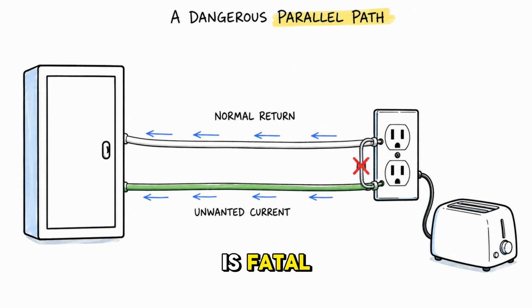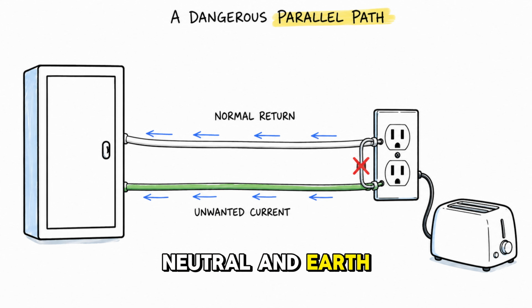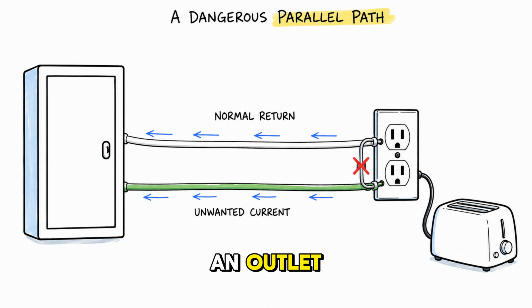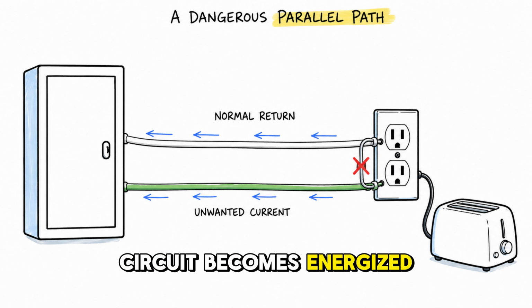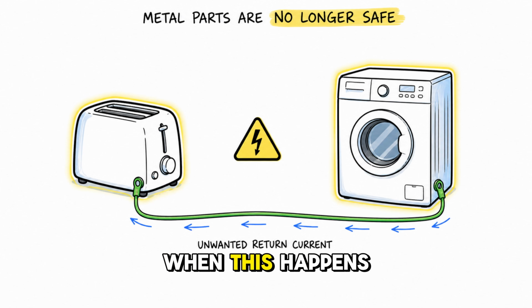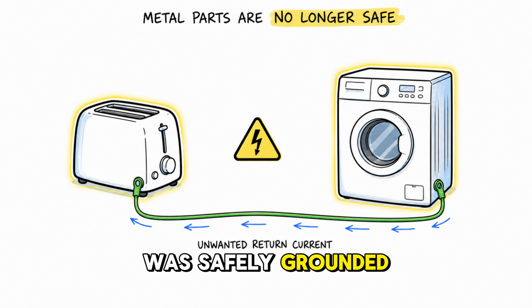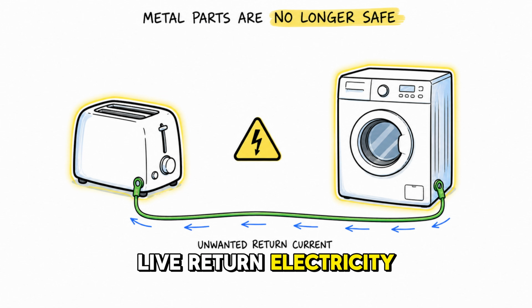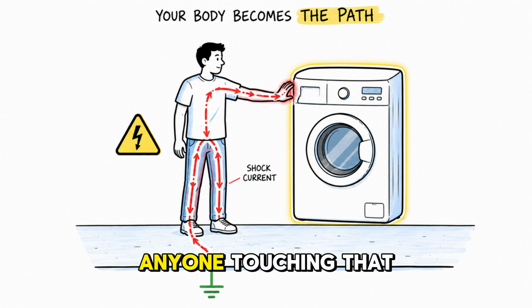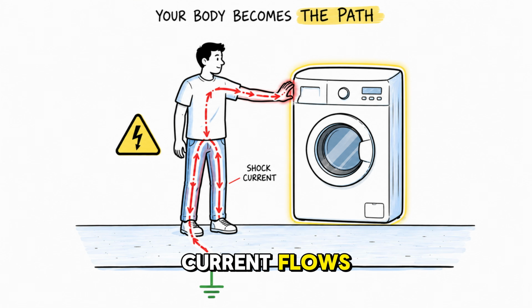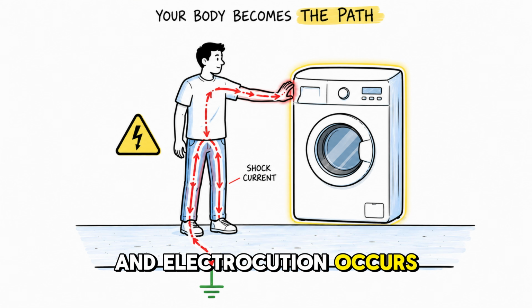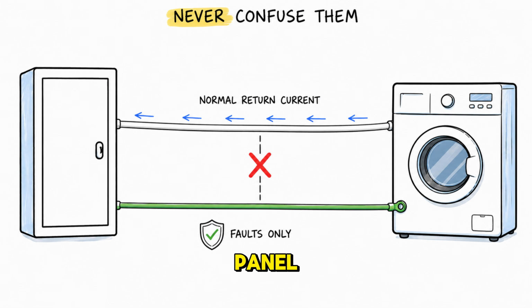Now here is why confusing them is fatal. If you connect the neutral and earth wires together at a subpanel or at an outlet, you create a parallel path. The earth wire in that circuit becomes energized with return neutral current. When this happens, the metal chassis of every appliance on that circuit, which you assumed was safely grounded, is now carrying live return electricity. Anyone touching that metal casing provides a path to the floor. Current flows directly through their body and electrocution occurs. Both wires connect back to the panel, but one carries current all the time and the other should never carry current unless there is an emergency.